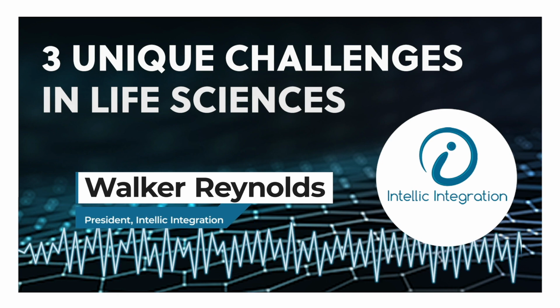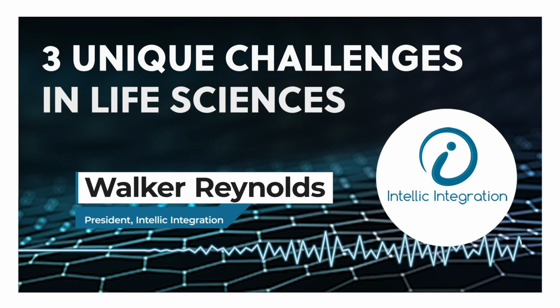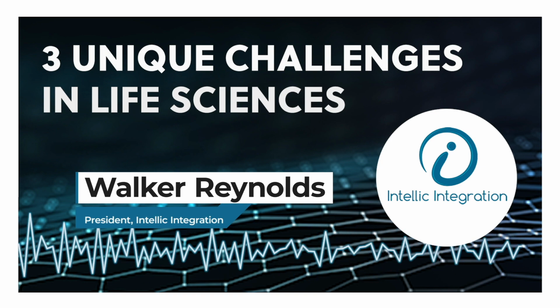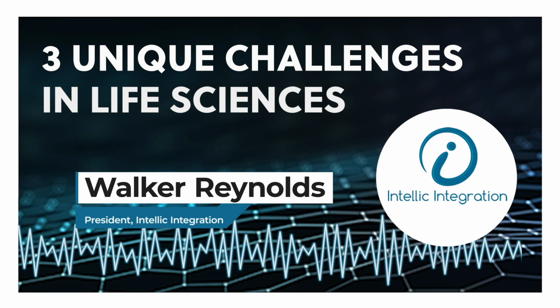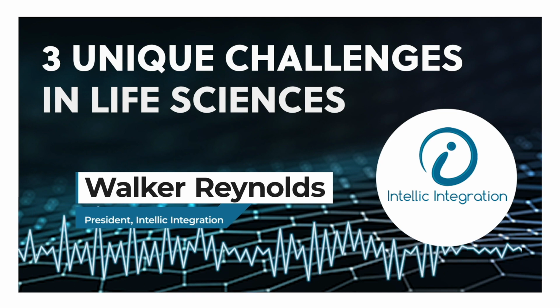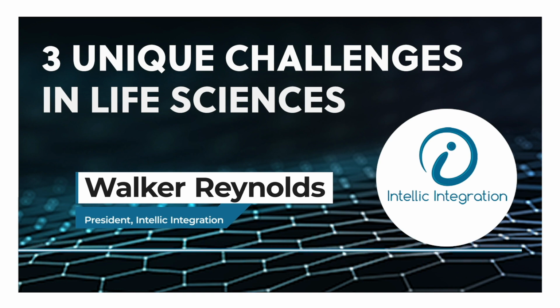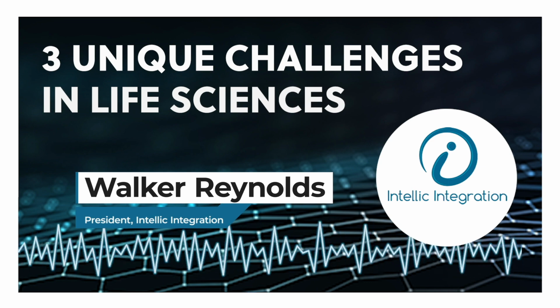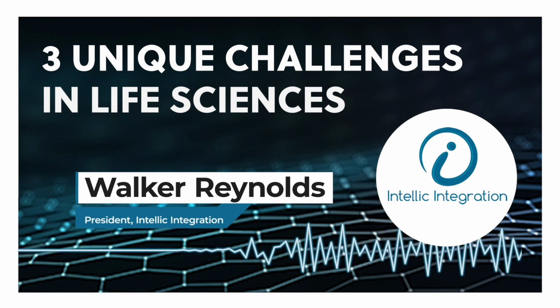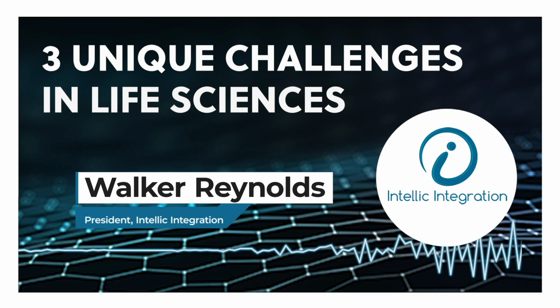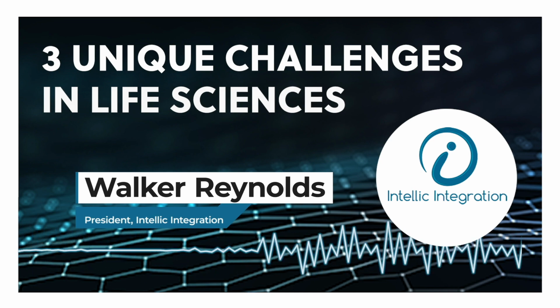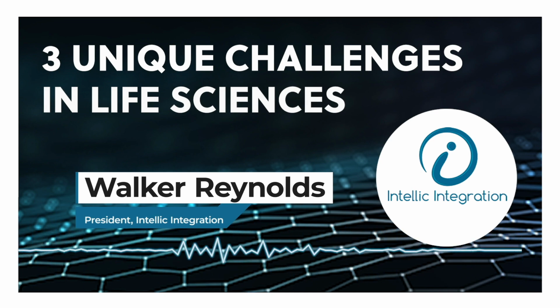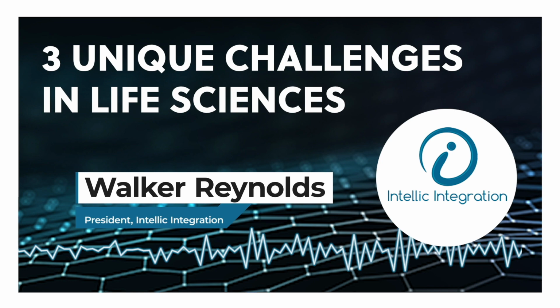80% of the work in life sciences is validation of each individual data point. So that's a huge challenge in digital transformation for pharma. The biggest advantage of moving to report by exception, edge-driven, and open architecture is that there's only one validation, and that is when you point the edge node to the broker. The only thing you have to validate is that it got to the broker in the correct form. The value was correct. You only have to do it one time. When you go linearly up the automation stack, it has to be validated at every handoff point. So that's number one. Validation is a big issue in life sciences.